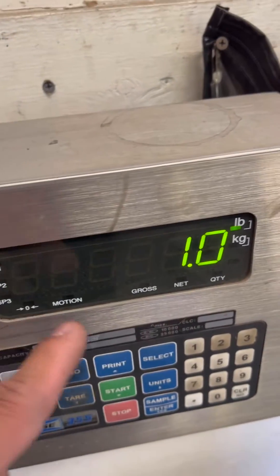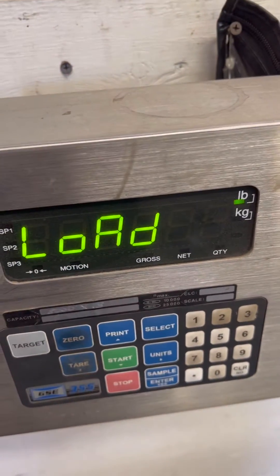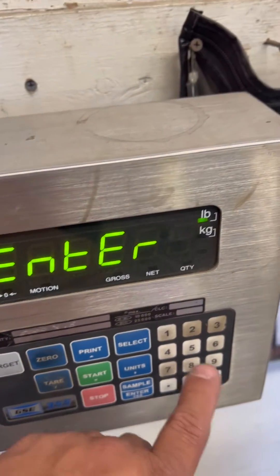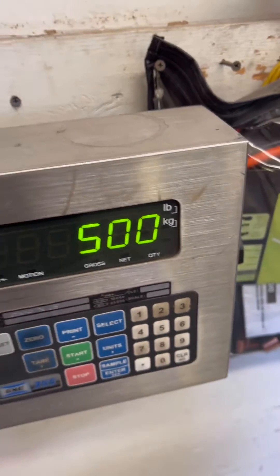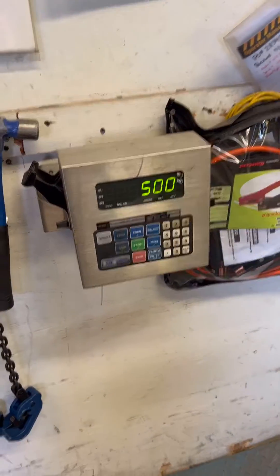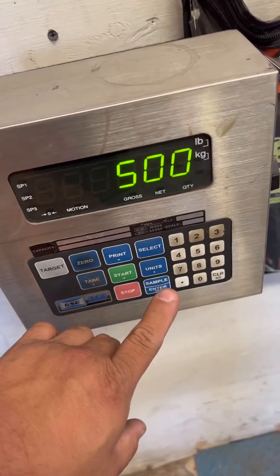That's your first zero. With nothing on the base, you're going to press enter. Then for your load, I'm going to put 500. You apply your load — once you apply your load for 500 pounds — and you press enter.